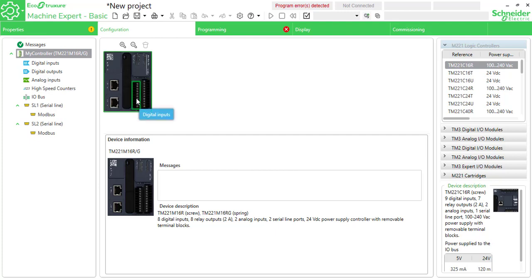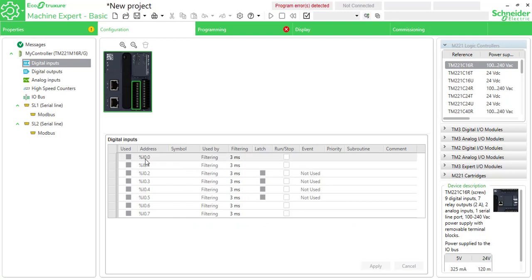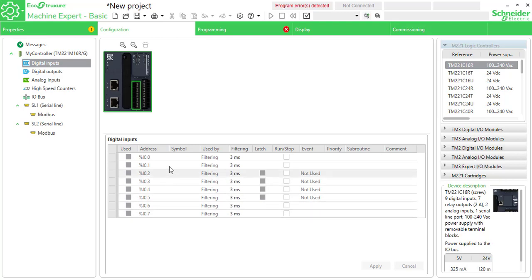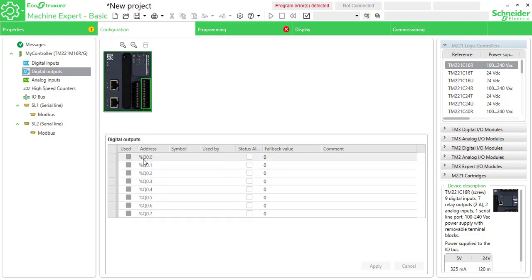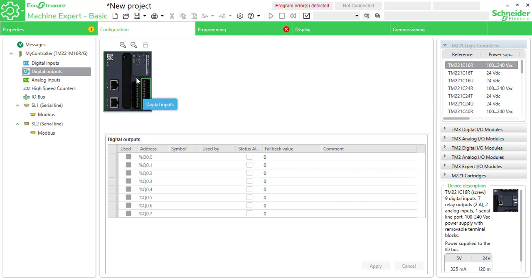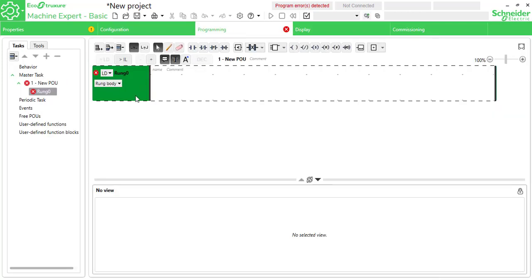Double-tap on digital inputs. You can see the digital inputs are %I column 0 — %I0.0, %I0.1 — this is the type of input addressing. For digital outputs, it will be %Q0.0, %Q0.1, %Q0.2, and so on. This is the input and output addressing configuration.